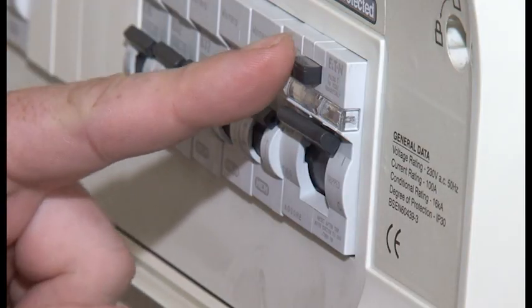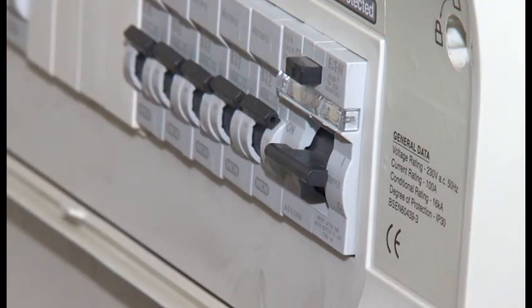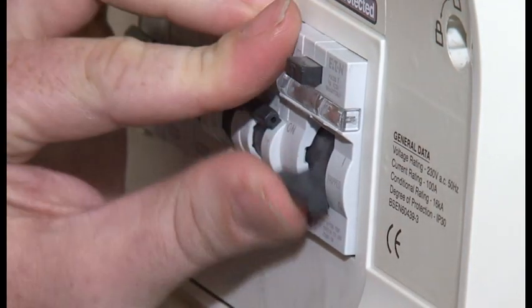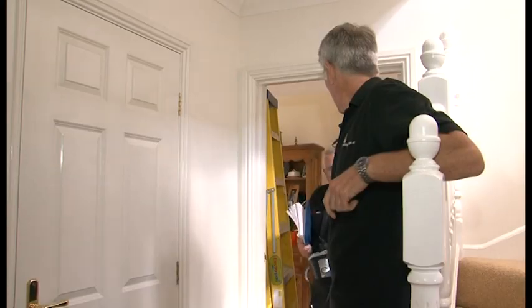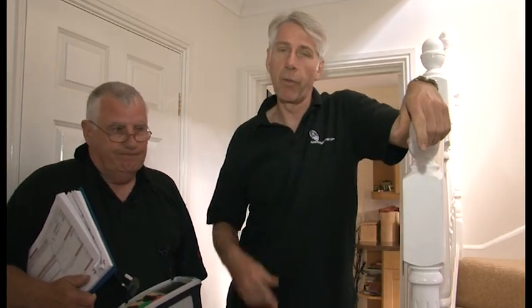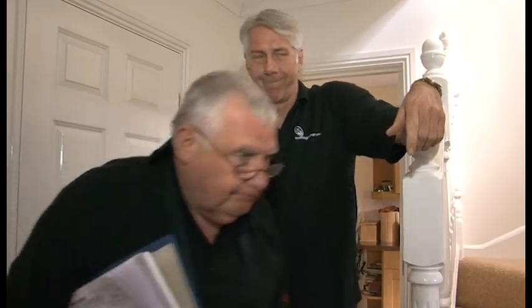Finally, for RCDs, it's important to check that the manual test button on the device also causes it to operate. All done? I think so, yes. Good result. We've now completed our EICR, so we'll do a quick check through the form to make sure we haven't missed anything, and then head back to the office.